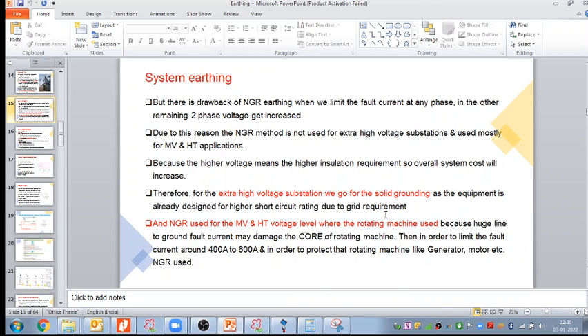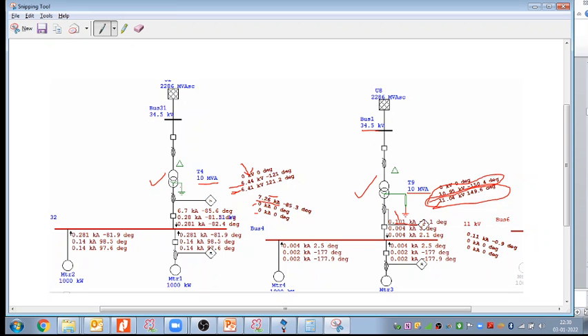So what is my statement here? For the extra high voltage substation I will not take NGR grounding. I will always go with solid grounding. Why solid grounding? Because my voltage remains the phase voltage, and although the current flowing is higher, I have already taken sufficient rating of the equipment. And there is no rotating equipment, so there is no drawback with this fault current.